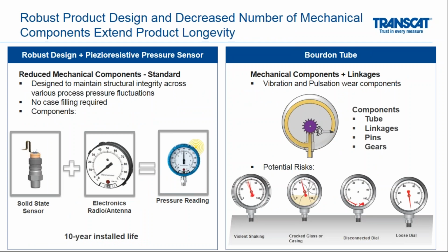And another piece is just reducing those parts. I mentioned how the wireless pressure gauge has a solid-state sensor, a piezo-resistive sensor. There's the actual electronics that ultimately move the needle, and that provides you the wireless pressure gauge. And because the needle is the only moving part, there's a lot less things that can go wrong here. It has a 10-year installed life as a result, based on its power module. And again, if you look at the bourdon tube with 9 different parts, there's many different mechanical pieces that can slip, that can fail, that can get overbent, over-torqued, whatever the case is.